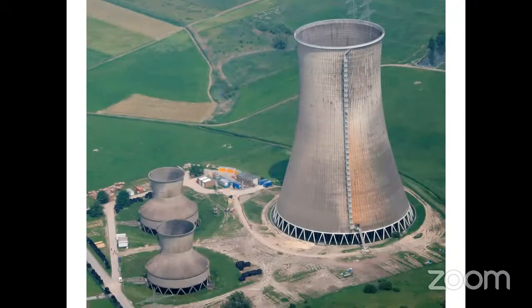Actually, the original Basin Bridge power station was having a cooling tower. And Mettur thermal power station is still having a cooling tower. And the 600 megawatt new power station in Mettur station 2 is also having a cooling tower. But in North Chennai, the 2x210 and 2x600 units do not have any cooling towers. The condenser is cooled by a once-through seawater system.